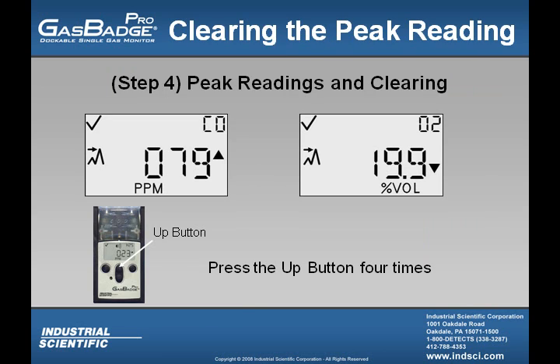And finally, the fourth step of operation, clearing of the peak readings. If the user is trying to clear the peaks, they must first press the up button 4 times, and then they see the mountain peaks with the arrow pointing right. The screen on the left shows the user what the peak reading screen would look like if they had a toxic sensor installed in the GasBadge Pro, and the screen on the right shows them what the screen would look like if the user had an oxygen sensor installed.